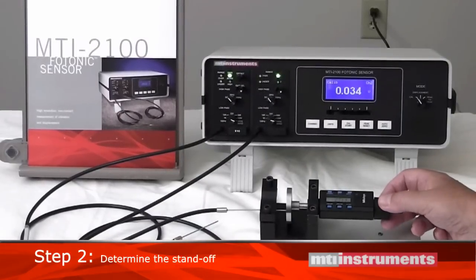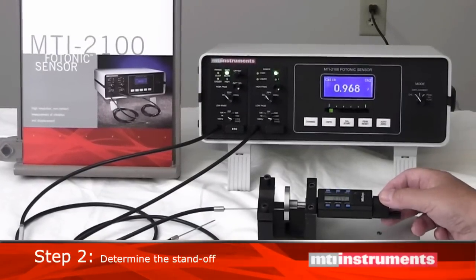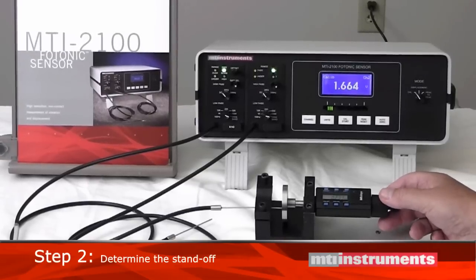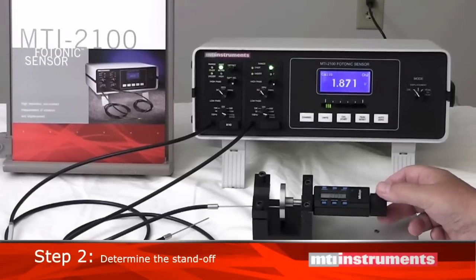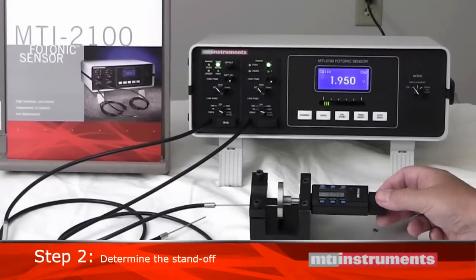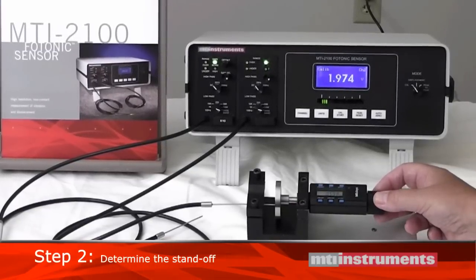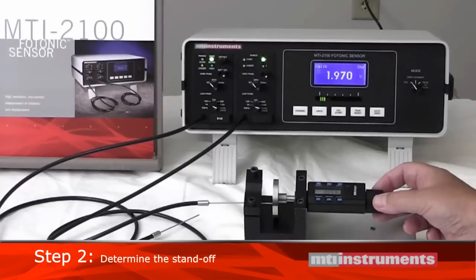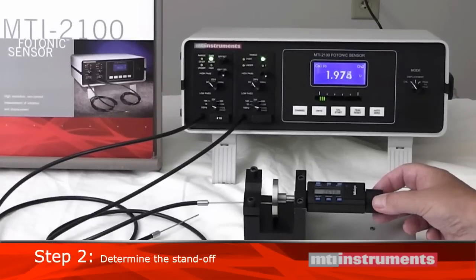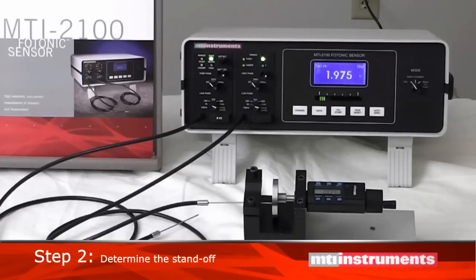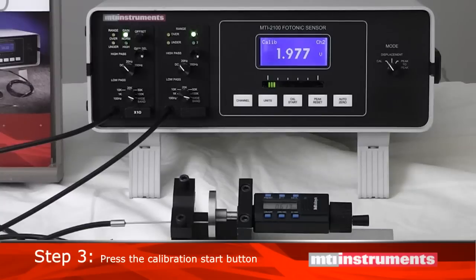Step 2, rotate the micrometer counterclockwise, and the LCD display will show the number increasing. Then we reach a point where the number starts decreasing. If needed, do a rocking motion, or clockwise and counterclockwise rotation, to fine-tune the maximum reading, and then stop. This is now at the maximum distance from the target. And our final step, push the Cal Start button.